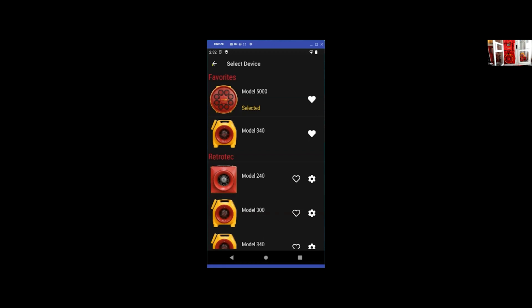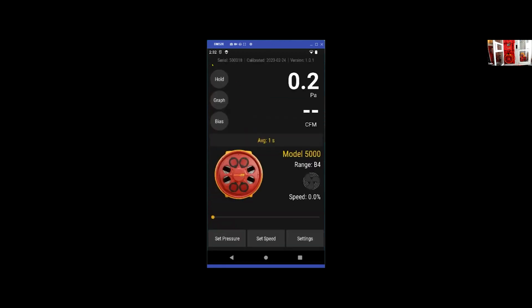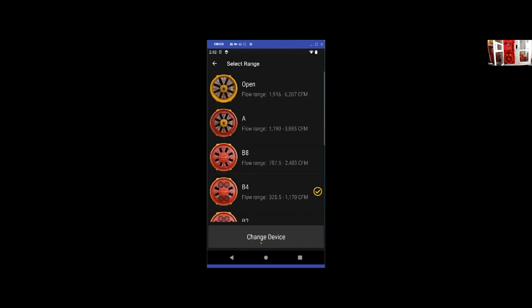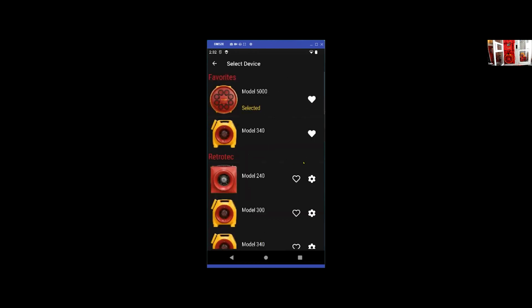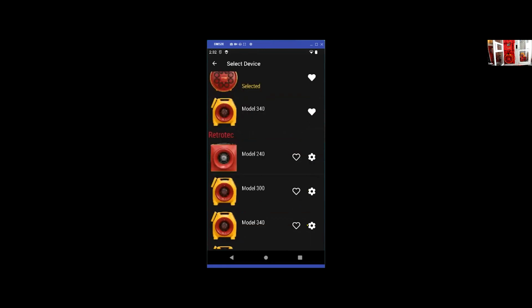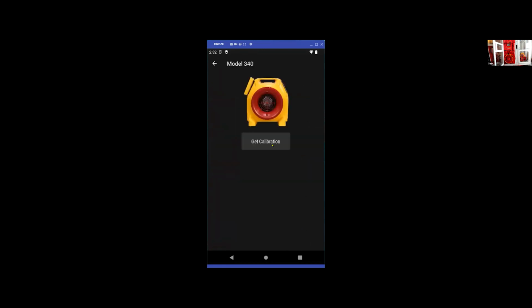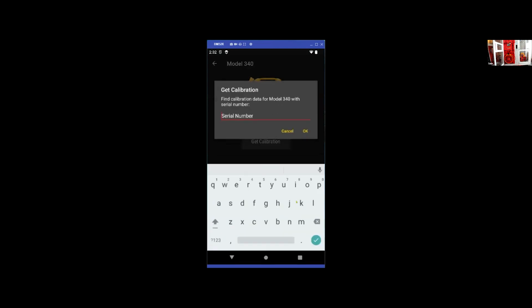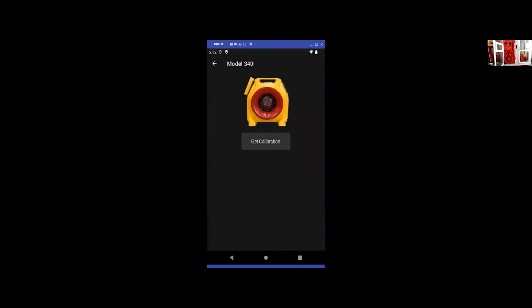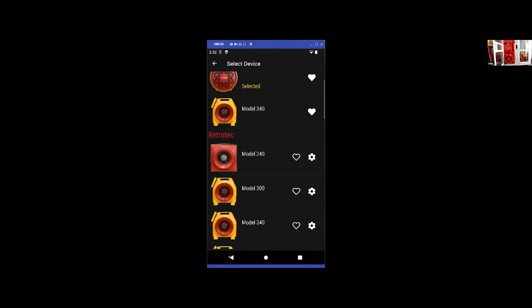The clarity of all the ranges is a lot better than what was illustrated on the previous devices. You'll see that settings icon next to each of those devices, which allows you to type in the serial number for the specific fan you have. It will actually pull down the flow data fits for the calibration for those fans by serial number from our cloud database, giving very accurate flow.